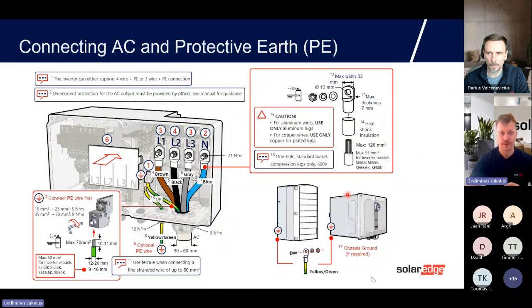Here, I don't want to go into very big details about cabling and so on. It's not about this. But number one, what you really need to remember when you work with aluminum cables is to make sure you do everything correctly. You prepare the cables, and you use the paste that avoids oxidation on the contact. Me and Iris just saw so many melted connectors because of poor conductivity. So please make sure you do a good job here and you have no issues later on. Grounding as well, very important.